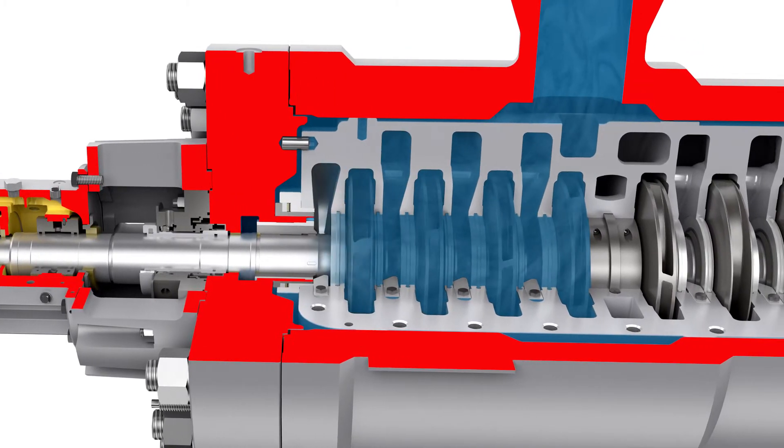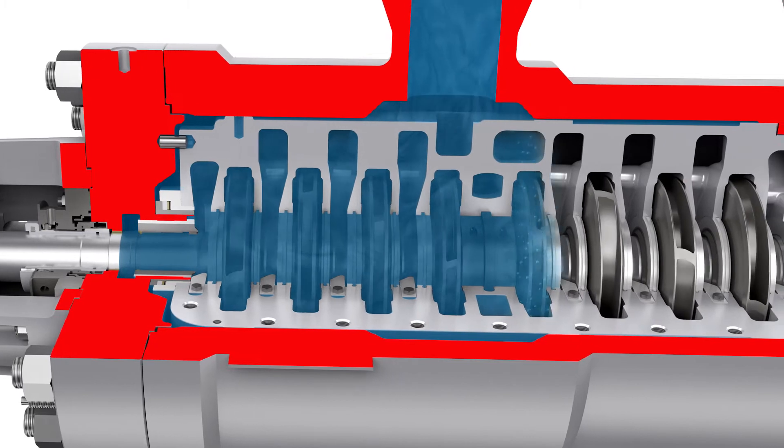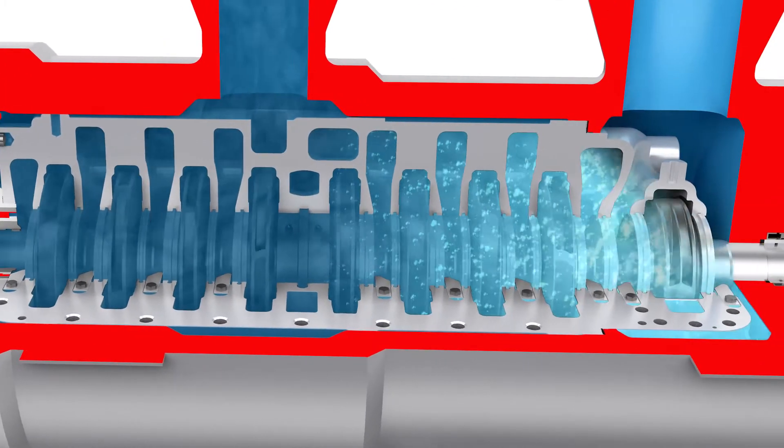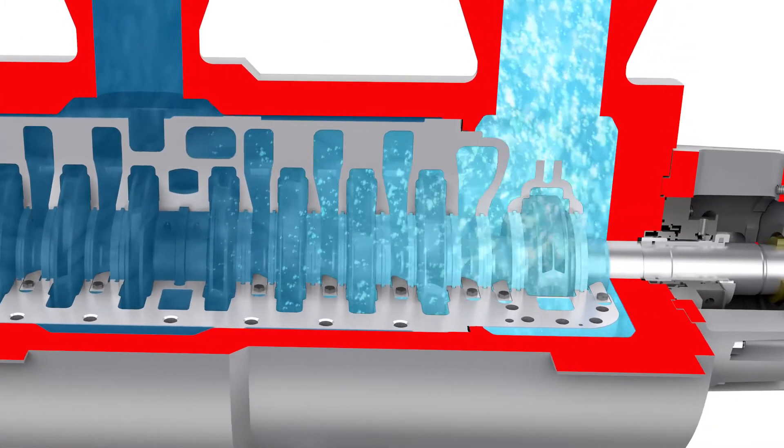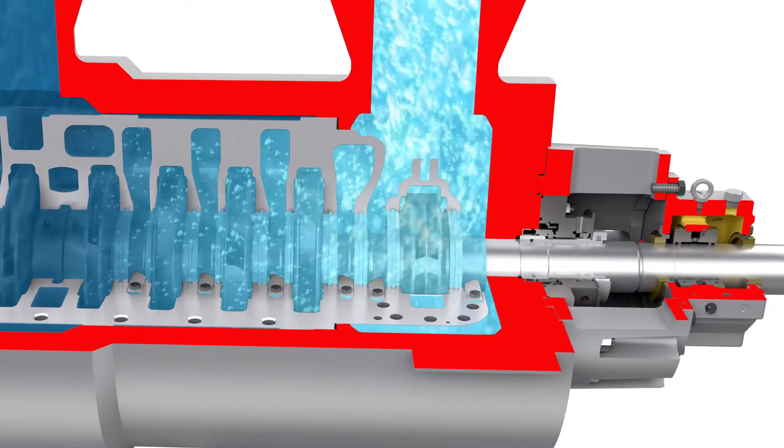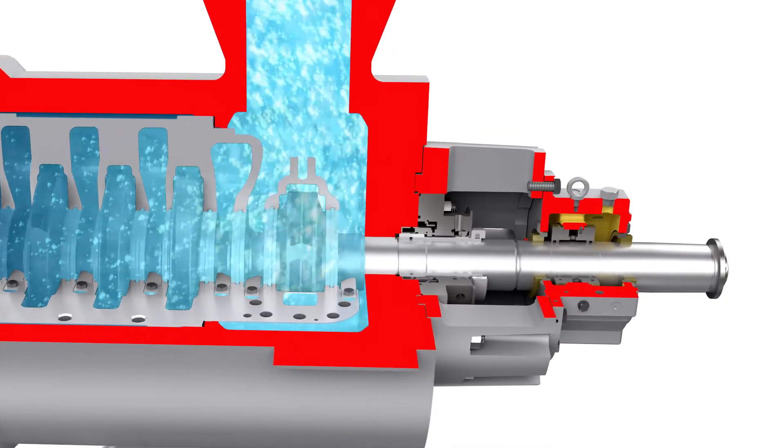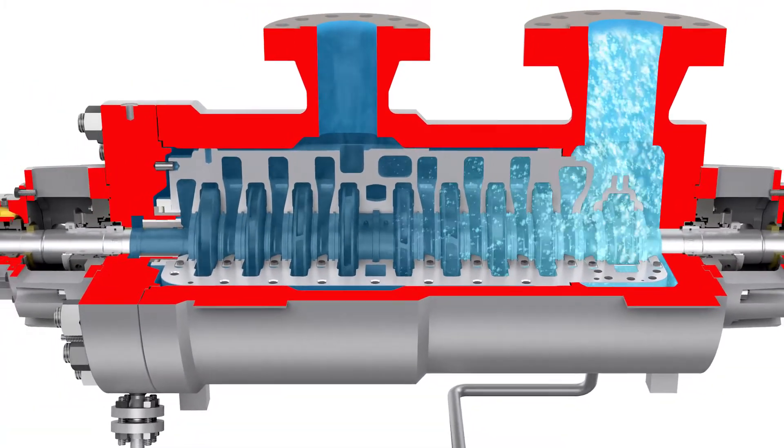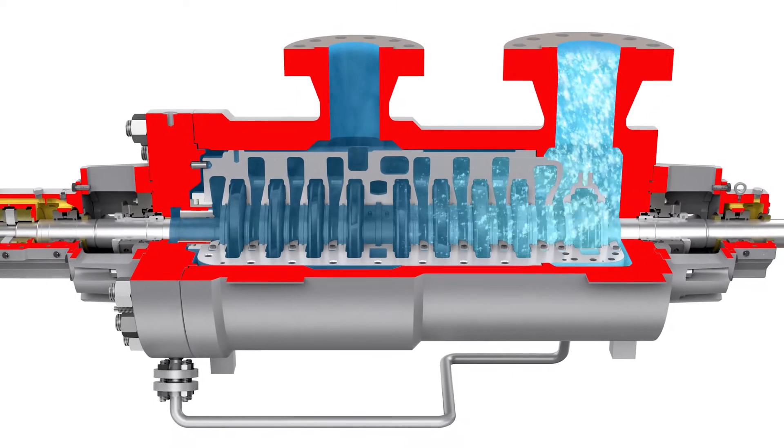However, effluent streams from reactors are not always single phase. Vapour evolves from the liquid as the pressure of the fluid stream drops across the HPRT. By volume or gas void fraction, the amount of vapour at the turbine's outlet pressure can be quite substantial, 60% by volume or more.